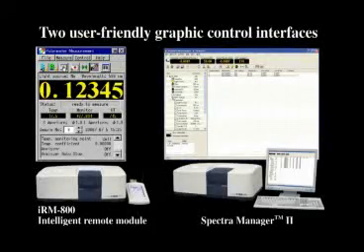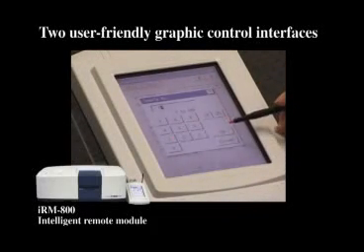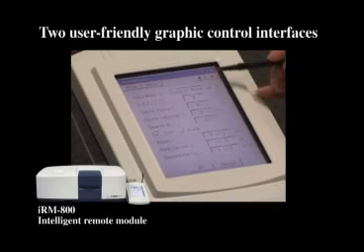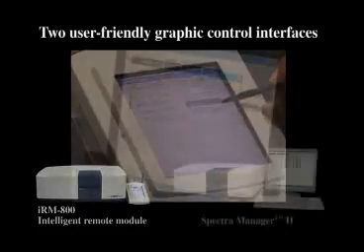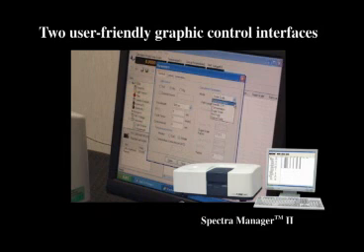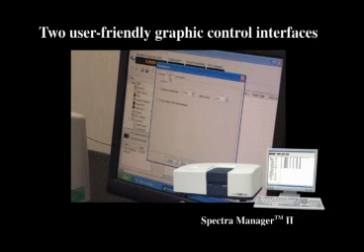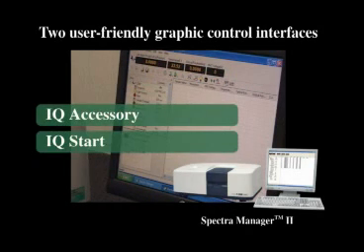Two user-friendly graphic control interfaces are available. The IRM's large touch screen guides the operator through all procedures. The obtained data can be printed using a USB printer or saved to a compact flash memory card for further processing on a PC. JASCO's unique cross-platform software, Spectra Manager 2, provides full system control and advanced data processing. Light sources and filters currently in use are automatically recognized. The IQ accessory and IQ start features streamline procedures using automatic accessory recognition and automatic program start.